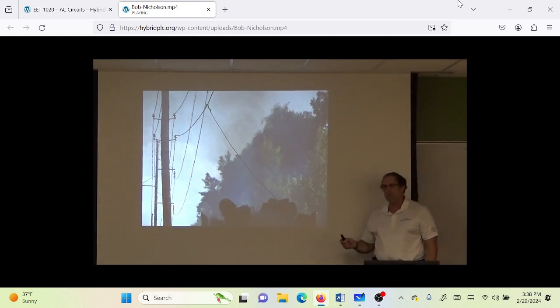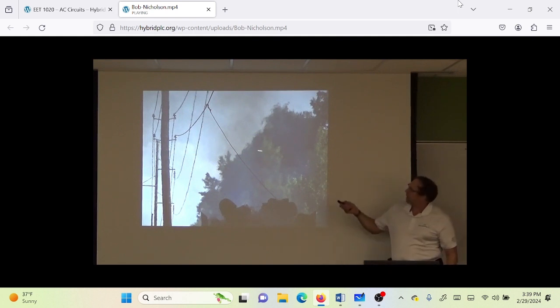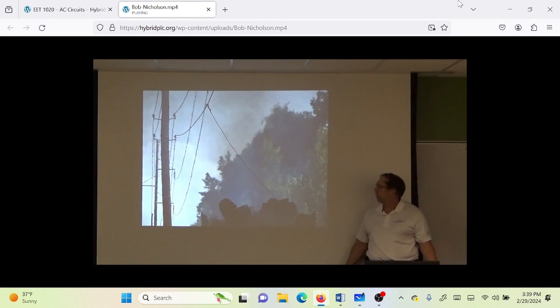Now, if you're at home, and the lights go on and off 3 times, you know why that is? There's a branch probably touching that. That's why they trim the trees. And what it is, it's a recloser or an electronic breaker turning it back on 3 times. It's trying to blow the branch up. And if the branch blows up, because the fault current would go here, down the branch, down the tree, to the roots of the tree, all the way back to the ground. And it would blow the branch up. After the third try, it stops, because it's something other than the tree. In this case, it can't blow this up.